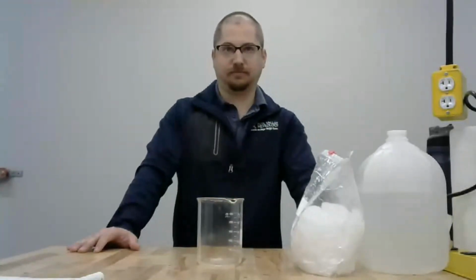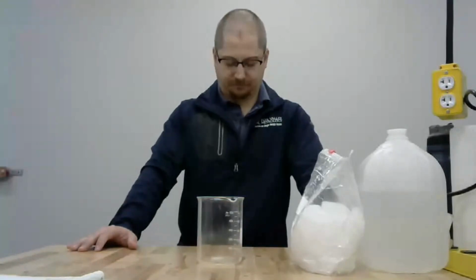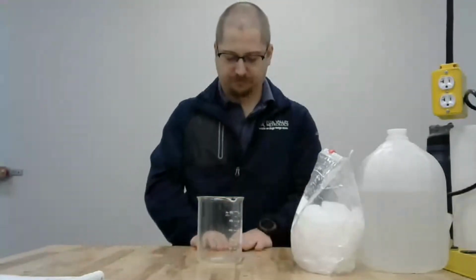Again, an ice point reference can be used to perform a quick verification of your temperature probes because the melting point of ice is the true reference that's going to be used for basically everything. That's what CJC is referencing or attempting to reference. So making a quick ice bath is defined by NIST. So when I say a quick ice bath, please do not discount the legitimacy of what an ice bath is. It is a NIST traceable reference point. So it is considered a physical constant at 0 degrees Celsius with an uncertainty of 0.01 degrees Celsius.